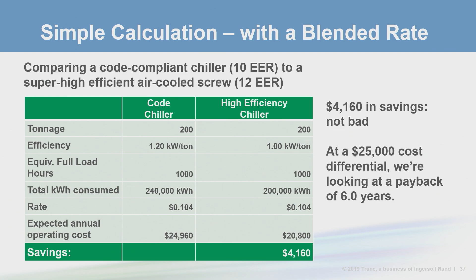If we use the blended 10.4 cents per kWh, you can see that we do get some savings from the high efficiency chiller here. Again, using nice round numbers to make our math easier, let's expect the unit to run at 1,000 equivalent full load hours in this example. And so the high efficiency chiller would save 40,000 kWh and about $4,100 in this simplified analysis. Given that we're looking at a $25,000 cost adder for the high efficiency option, going with the more efficient chiller would yield a simple payback of 6.0 years. It's not terrible. Maybe the school district would bite here and make the efficient choice.